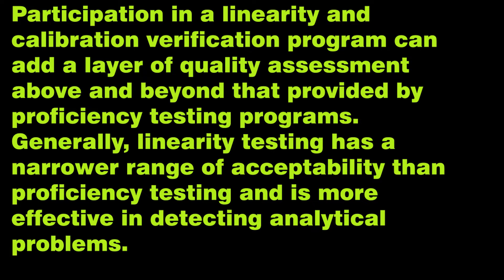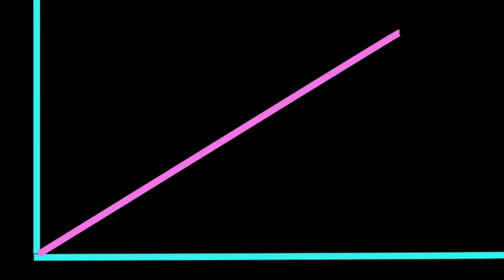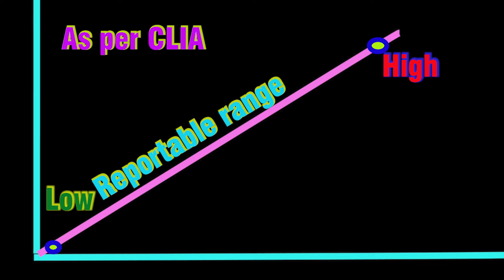What is the range we need to check? The reportable range, as per CLIA, is defined as the span of test results — low end to high end — that the laboratory can actually verify the results of a clinical test system for a given assay. The reportable range includes the sample dilution for high levels of analytes, for example HCG beta.